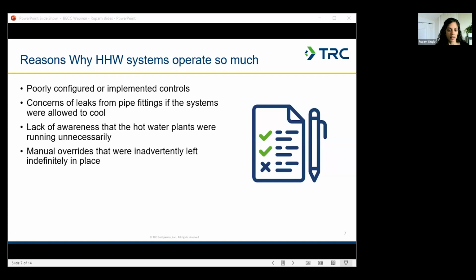And then these systems could be operating nearly 24/7 really just due to lack of attention. So these hot water systems often don't get the attention that they require. So there may be a lack of awareness that the hot water plants are even running when they don't need to be. Or maybe a building operator manually set the system to run over a weekend, say for a special event in the building, and then that system was never returned to its original control, and then it just continued to operate 24/7 after that.